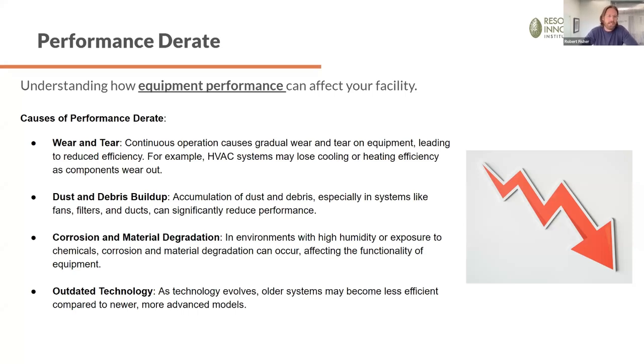Even on the outside heat exchanging equipment, every place I've worked that has chillers and/or evaporative coolers, there's one or two times a year the trees are shedding everything, like cottonwood and things like that, and all of a sudden it just gets blocked up and stops working very well. So you want to keep a check on that.